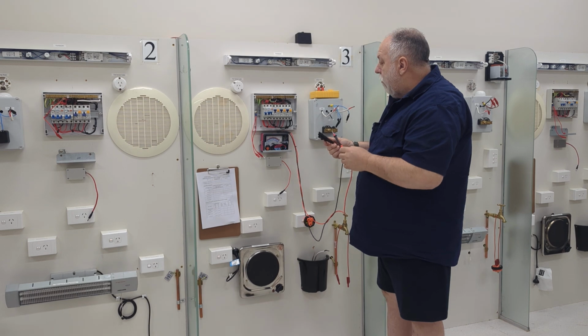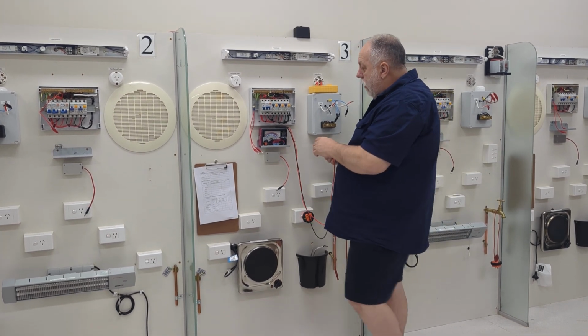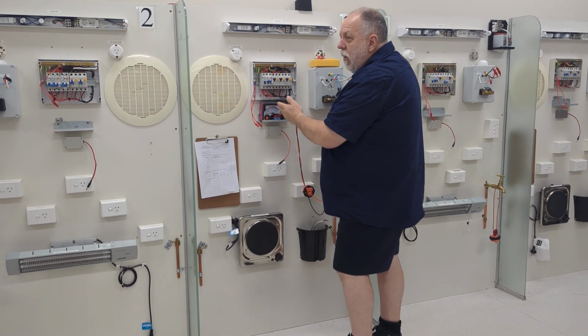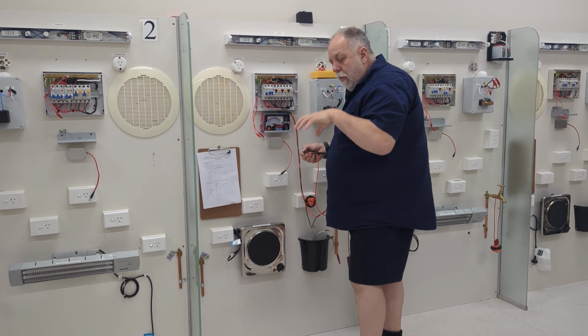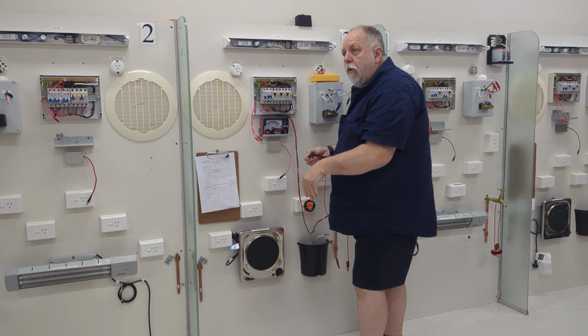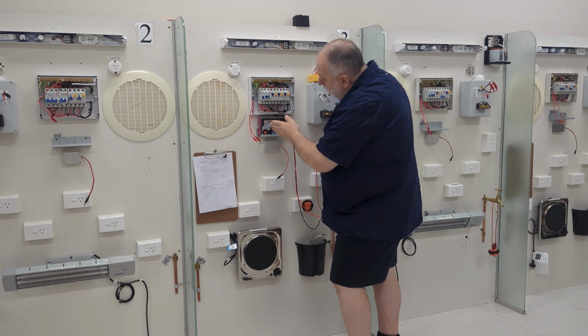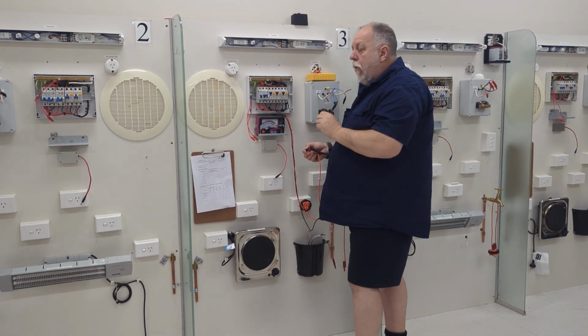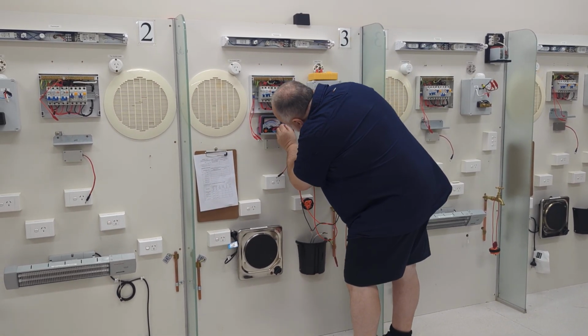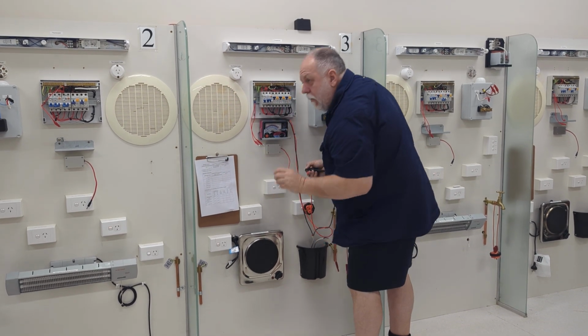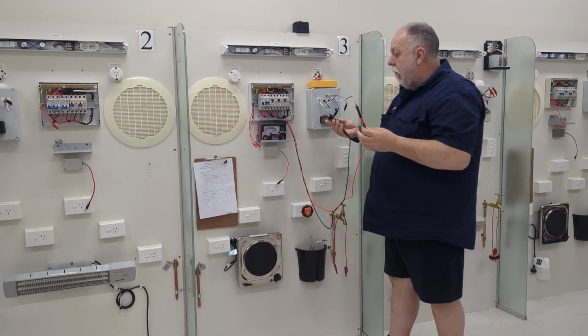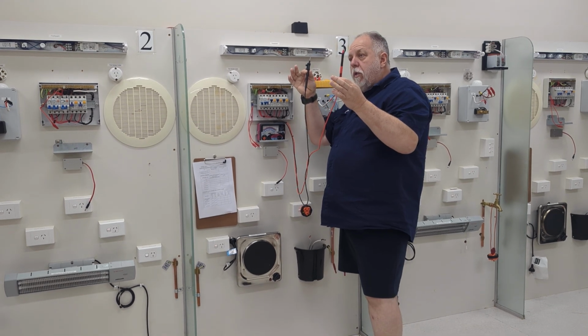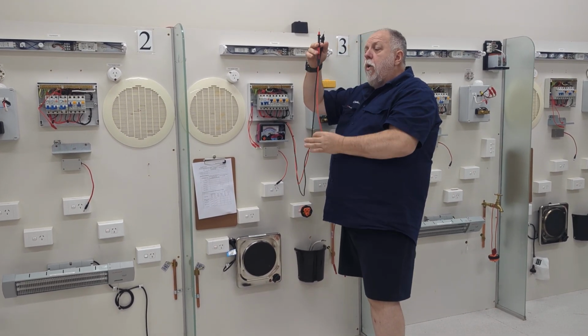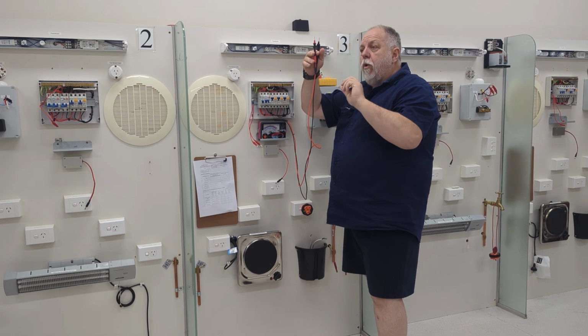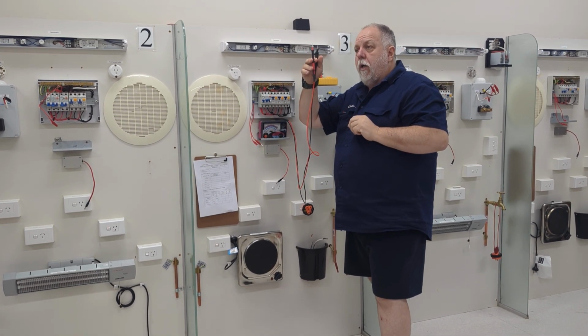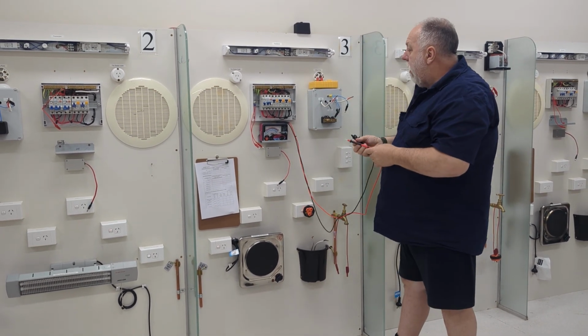All right, so the first thing I'm going to do is short my leads together. I read zero. When you're looking at a meter to zero, it's better to look at it down on a bench and looking over the top of it. Do you understand what I'm getting at? If you start looking from the side or this or that, it might not be quite on zero. So I'm looking at it from here. It looks like it's on zero, but when I go to the front, I've just got to give it a little whisker and I'm done on zero. Now I've zeroed it, I've taken the resistance of my leads out. If this lead was a 20 metre lead, I would have now removed the resistance of that 20 metre lead. Okay? All right, I've zeroed it out.